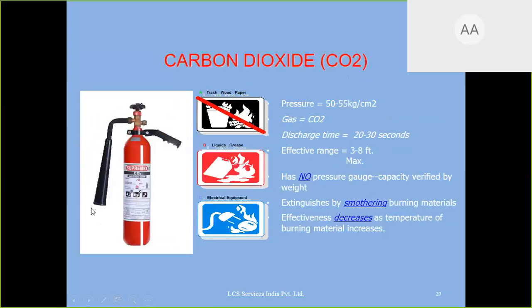This is known as the horn. Here the diameter is less, here it is more. In CO2, you get the larger diameter because the pressure is so high. I want to reduce the pressure when it comes out. Otherwise, if I keep the same diameter, the pressure is so high it will hit and reflect back, go somewhere else. That's why in every CO2 we use the horn to reduce the pressure. So you have also seen this video. CO2 can be used for B or C class, and DCP can be used for any type of small fire. CO2 can also be used only when it is a small fire. If you act at the initial stage, it can be controlled. Otherwise, the fire becomes big and you cannot control it.